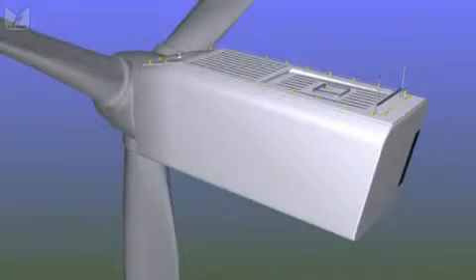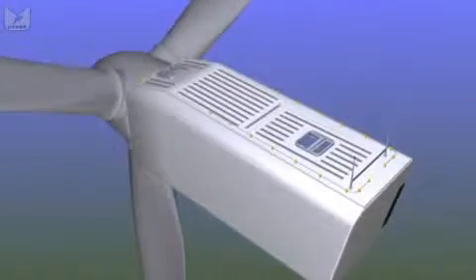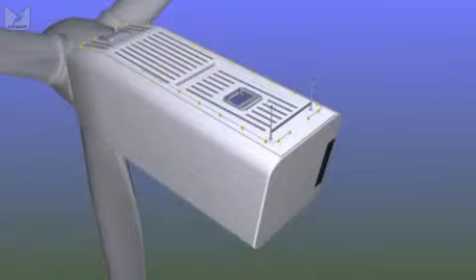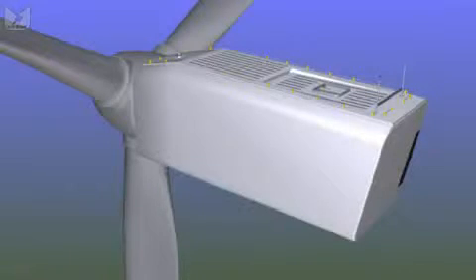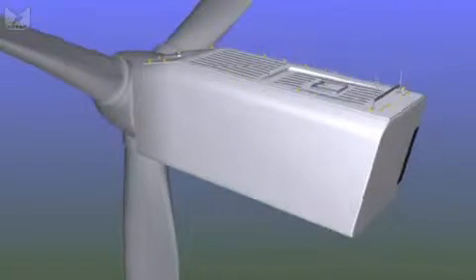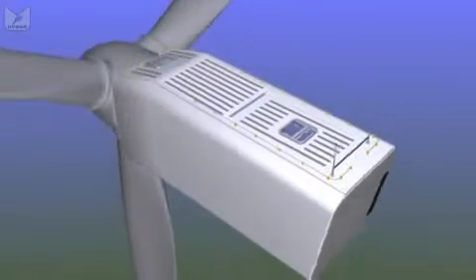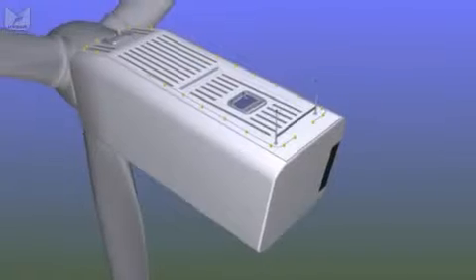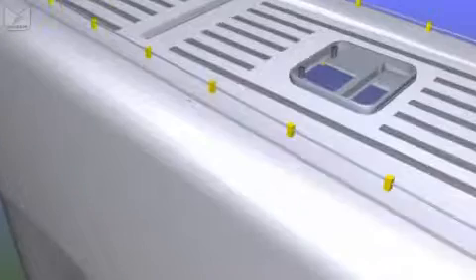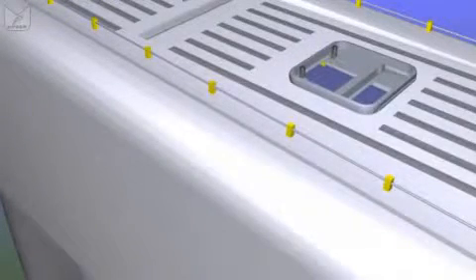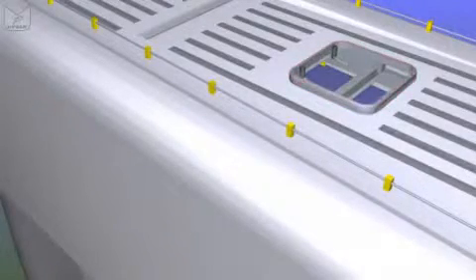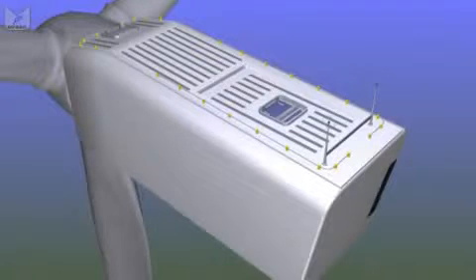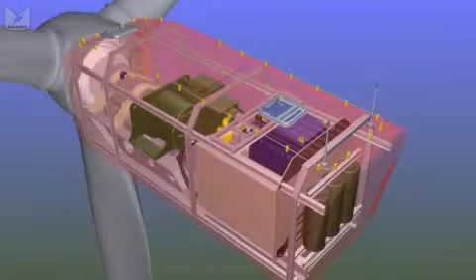And in our example, we're looking at a typical design used by a number of manufacturers, where we have a nacelle that's 3 metres high, 2.5 metres wide, 7 or 8 metres long. It's a fiberglass box about the size of a site hut. As before, we have our wind sensors on the roof as far away as possible from the dirty air cast off by the blades as they spin round. This design is just a fiberglass box with a flat roof. We access the roof through a couple of skylights. Some designs are like before, big cylinder with two opening doors. Some have an entire roof section which opens rather like an old camper van.